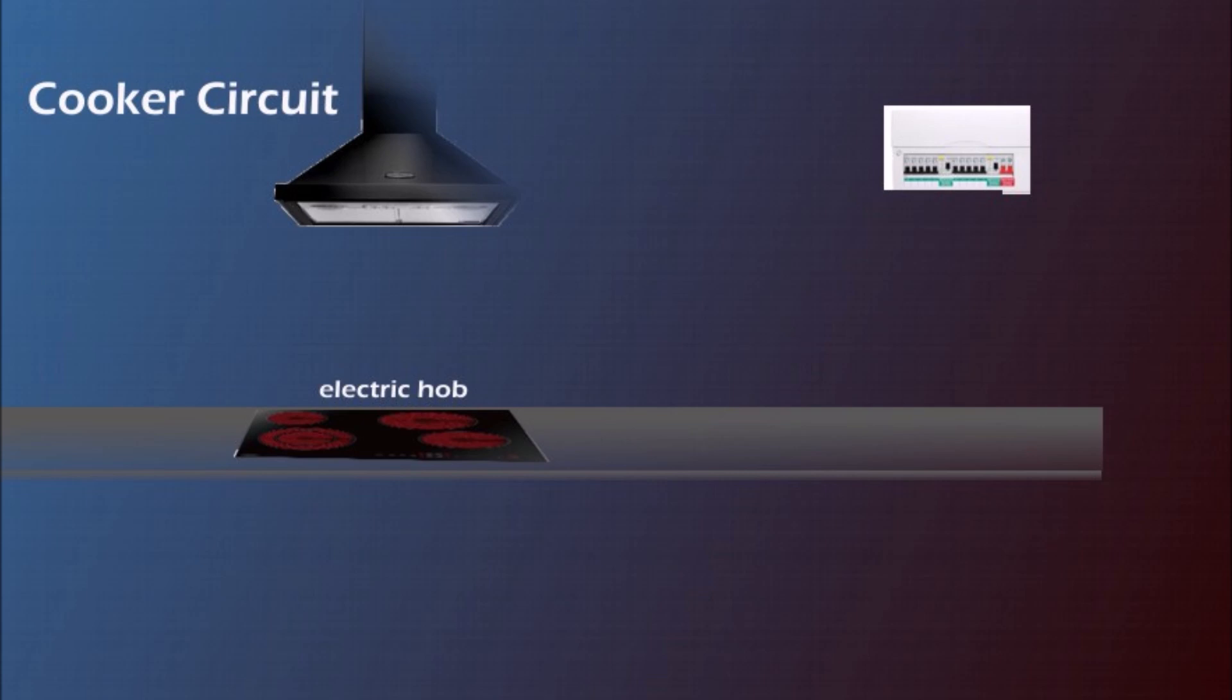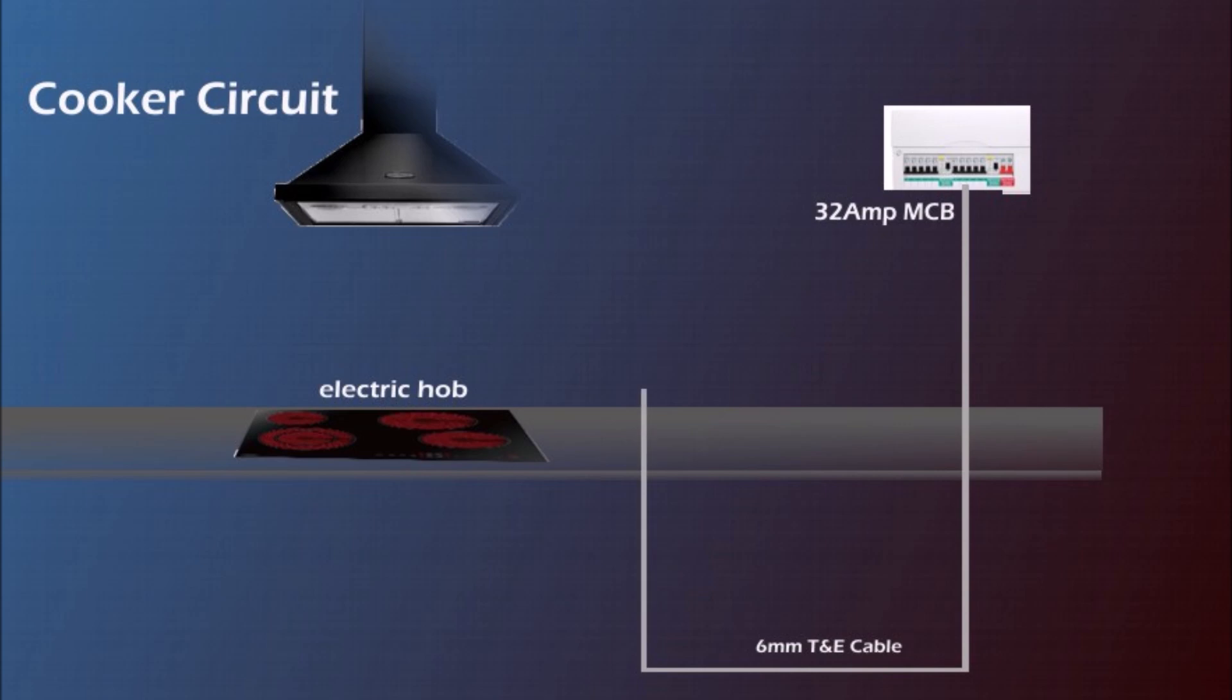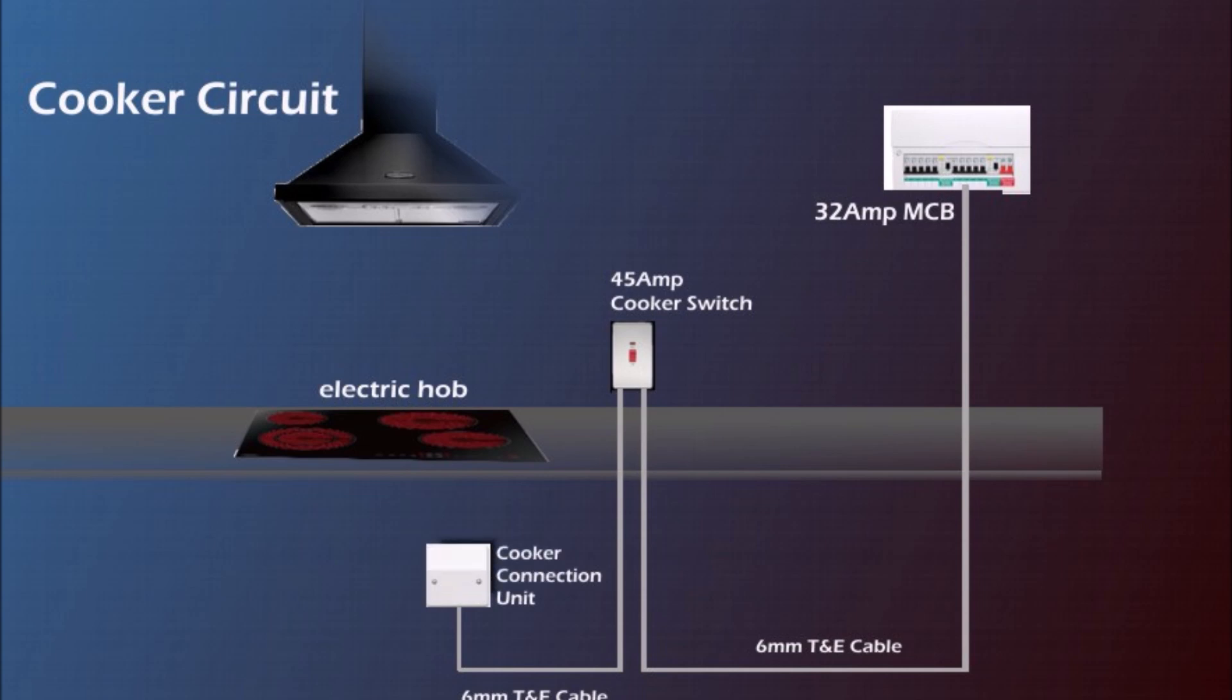Nowadays we need cooker circuit mainly for the electric hobs as they draw quite a lot of current. This has to be dedicated circuit straight from the consumer unit. So we've got 32 amp MCB at the consumer unit, then we need to run 6mm twin and earth cable to the 45 amp cooker switch located at least 30 cm from the hob and from this switch we run the same 6mm cable to the cooker connection unit that is usually under the hob. And then with the heat-resistant flex we wire the hob to cooker connection unit.